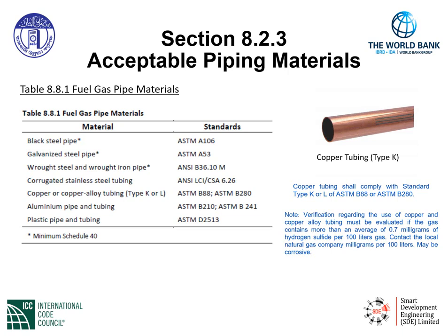Hydrogen sulfide has a corrosive effect on copper materials. So it's advantageous to understand that initially before selecting materials for the gas piping system.